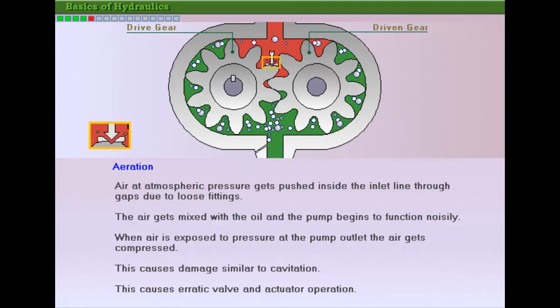Air traveling downstream causes erratic valve and actuator operation. Low oil level in the reservoir, as well as leaky fittings, can also cause aeration.